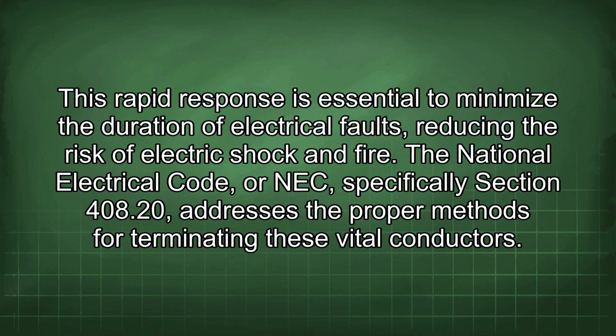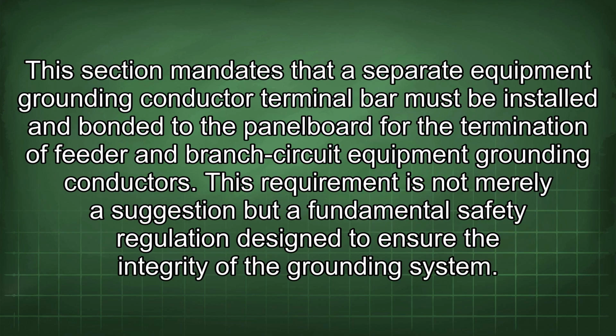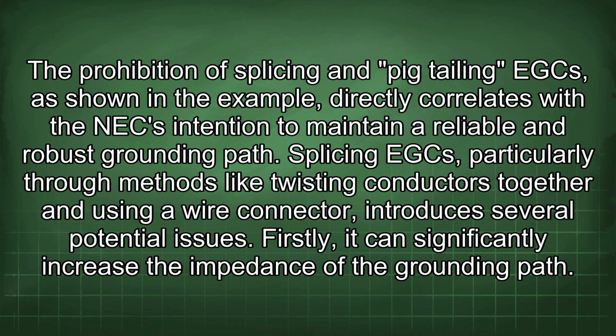The National Electrical Code, or NEC, specifically Section 408.20, addresses the proper methods for terminating these vital conductors. This section mandates that a separate equipment grounding conductor terminal bar must be installed and bonded to the panel board for the termination of feeder and branch circuit equipment grounding conductors. This requirement is not merely a suggestion but a fundamental safety regulation designed to ensure the integrity of the grounding system. The prohibition of splicing and pigtailing EGC, as shown in the example, directly correlates with the NEC intention to maintain a reliable and robust grounding path.